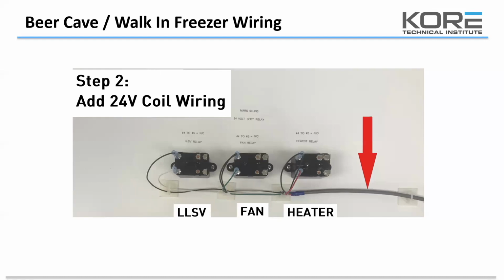wire these up to fail-safe in cooling mode. So on the liquid line solenoid valve and on the fan, we will wire from 4 to 5, the number 5 terminal going to the fan or to the liquid line solenoid valve itself. On the heater, we don't want that to fail safe on, so we wire the load side to number 2. That is the normally open contact.